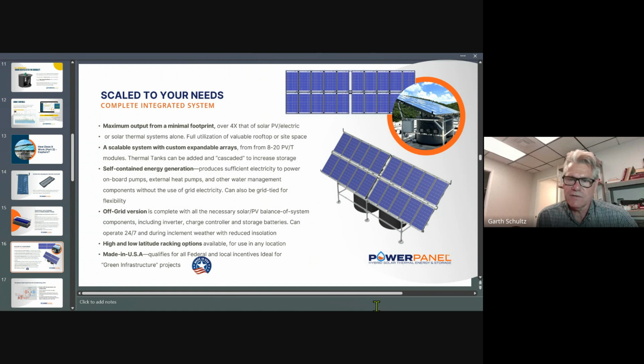So what's in front of you right there, that 20 module array, that looks like 12.7 kilowatts of thermal power and 2.7 kilowatts worth of electrical power. Energy storage underneath that array set is at 700 gallons. And at a 35 degrees C temperature differential, that looks like 108 kilowatt hours of stored energy. So effective capture plus effective storage.